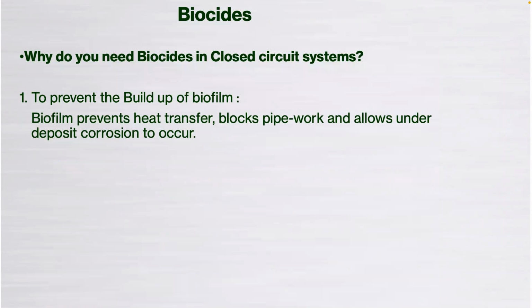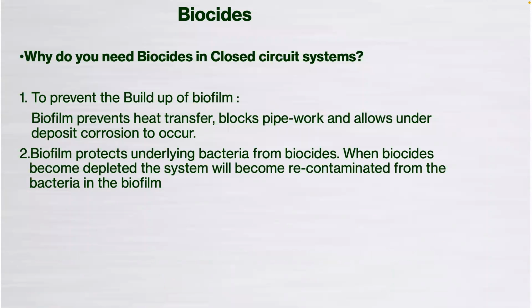And then we have biocides. So we talked about inhibitor to control corrosion and fouling, but then we have biocides. And a biocide, think of it, it's an antibiotic. Okay, so if we're filling a system up for the first time, we really probably want to be adding a biocide to the system. Mains water that we drink, municipal water that we drink, generally has low levels of bacteria, nothing hopefully pathogenic, but under stagnant conditions, they grow at a logarithmic rate, and they create these biofilms. So treating the water before it comes in, and certainly monitoring, prevents the buildup of these biofilms as well, because biofilm will protect bacteria from biocides.